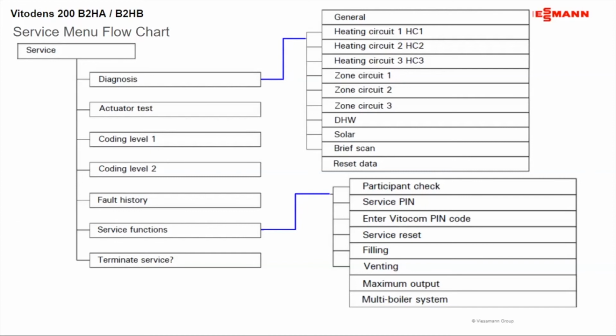Maximum output: say you get to the job and it's going to high fire, but it's snuffing out. Could be your gas screen is dirty, or your gas piping is too small. What you could do there is reduce the maximum output of your heating, and we'll keep it running until you can get out there and either upgrade your gas piping or figure out why you're not getting enough gas to the boiler.